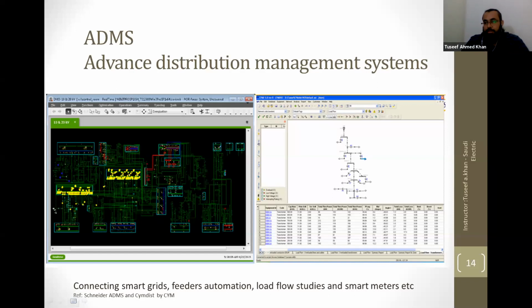Another thing, you have to check the quality of data for both real-time operations and planning purposes—cable length, resistance, and transformer data. If you're familiar with load flow software, you'll have an equipment database and a network database; these are different sets of data. You need to ensure the data quality is good, because if the quality for your network builder is poor, your load flow study results will deviate too much. It's all about your threshold value and tolerance level for accuracy, so data quality is very important.